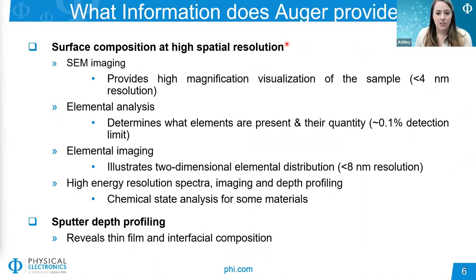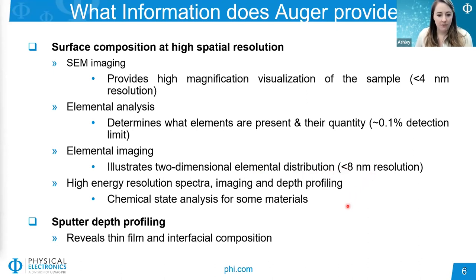From AES, you can get SEM images that provide high magnification visualization of the sample down to about 4 nanometers in spatial resolution. You can also determine which elements are present on the surface and their quantity, with a detection limit of about 0.1 atomic percent for most elements. We can get two-dimensional elemental distribution with elemental imaging at less than 8 nanometers spatial resolution, and chemical state information for some materials using high-energy resolution analysis. Furthermore, we can sputter depth profile materials to reveal thin film and interface composition, using a monoatomic argon ion gun that can also serve as a low-voltage flood gun to mitigate charging on insulating samples.